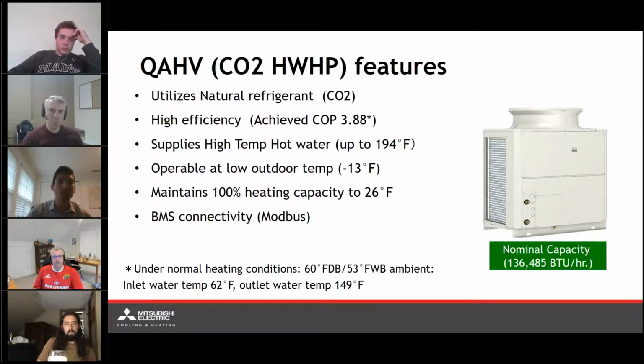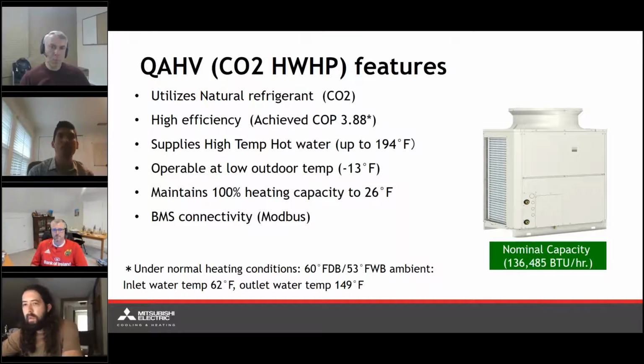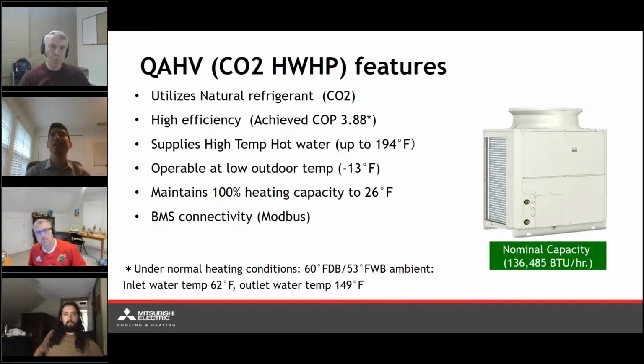So for the QAHV, the way we're going to be accomplishing this substantially high heat output is by using a high pressure refrigerant, CO2. So CO2 refrigerant, from my previous life when I was working in commercial refrigeration, we often saw CO2 in critical low temperature applications where we needed to maintain spaces close to 0 or well below 0 in freezer farms or things of that nature for large 100, 200 ton types of systems. So we're bringing that CO2 technology into a commercial 3-phase hot water heat pump system.